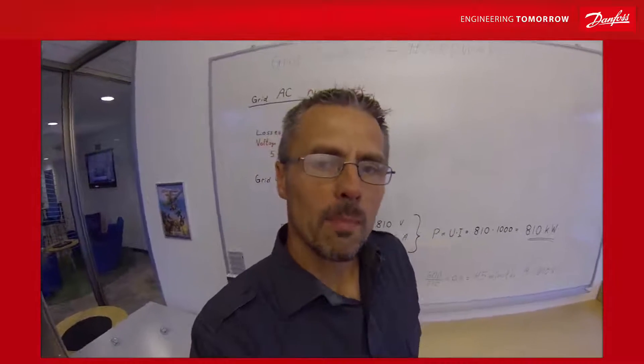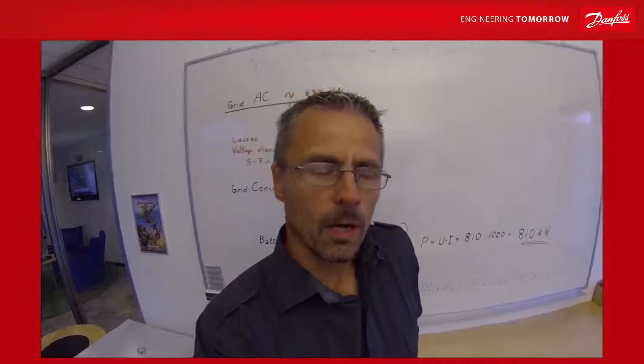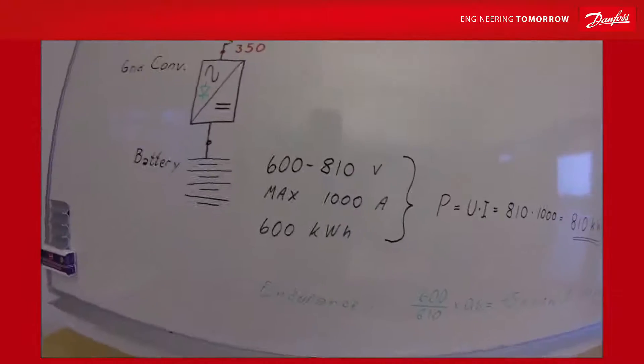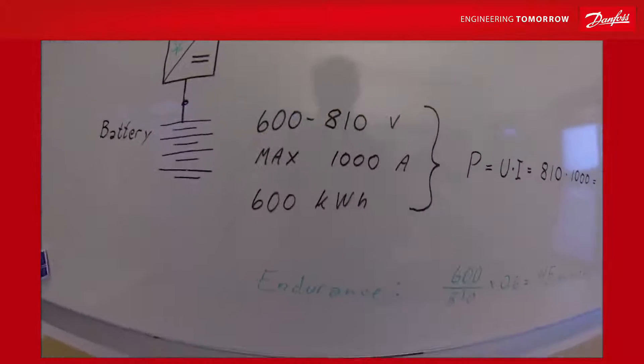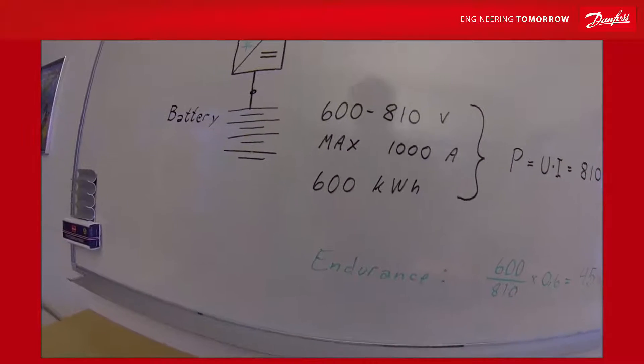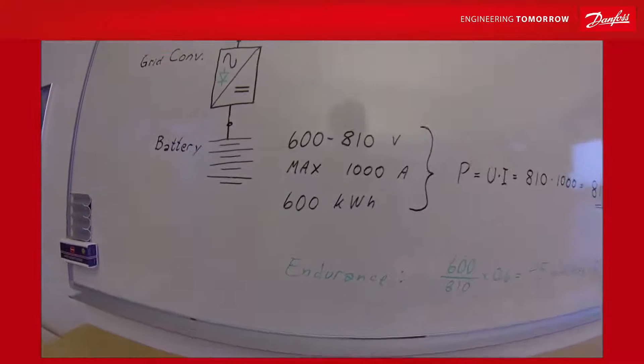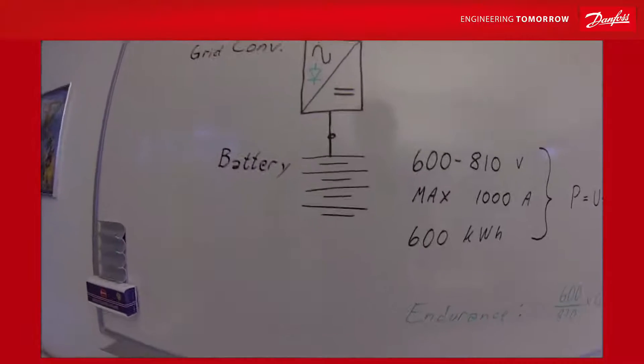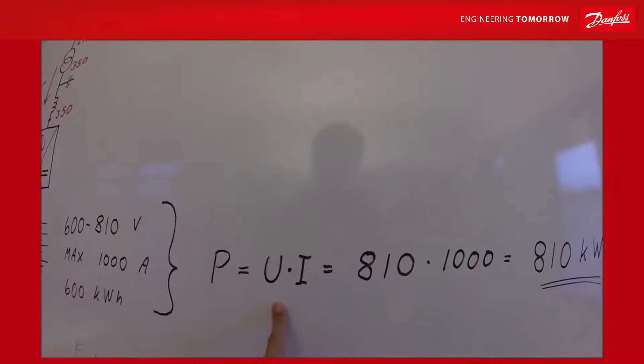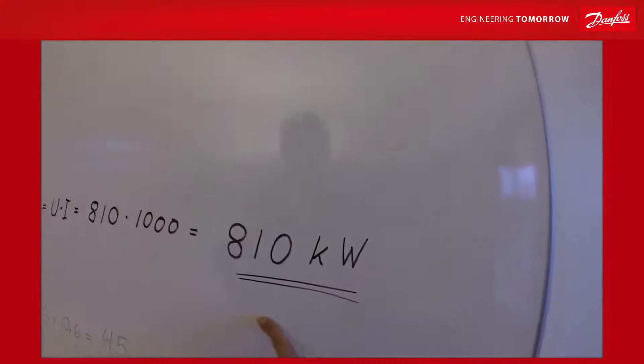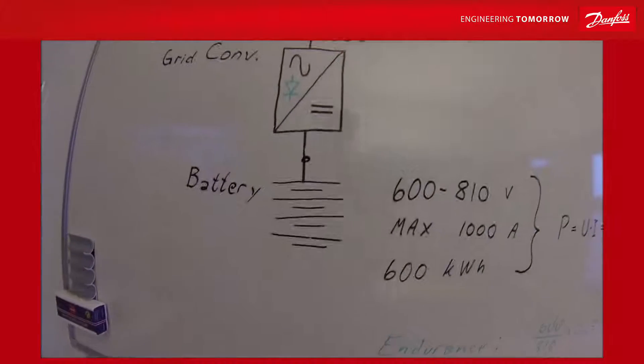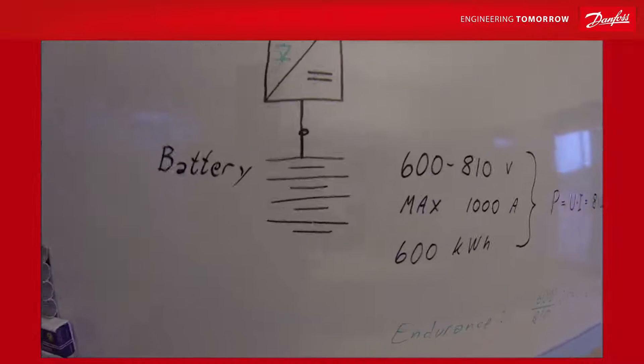We're now going to take a look at the dimensioning of the drive and the transformer, how many kilovolt amperes and how big drive it should be. It can deliver 1000 ampere both for the discharge and the charge, and total capacity is about 600 kilowatt hours. How many kilowatts will that be? It will be the power will be voltage multiplied with the current, and you will deliver 810 kilowatts with this battery. So it's typically a battery for a thruster on a DP class ship.